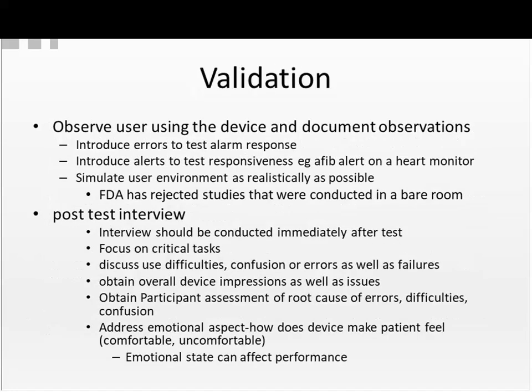Okay, validation. As I said, we're going to observe the user using the device and document the observations. As part of that test, we'll introduce errors to test alarm response if that's appropriate. We'll introduce alerts to test responsiveness.